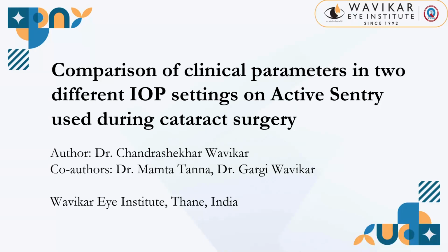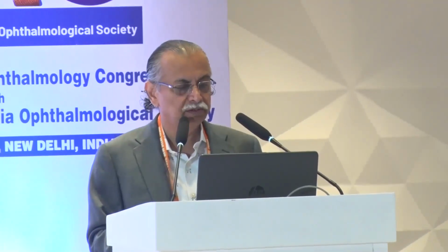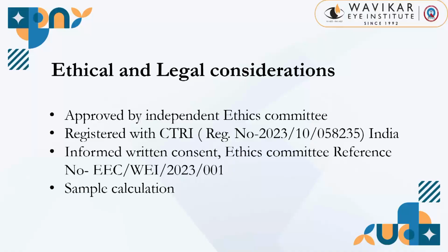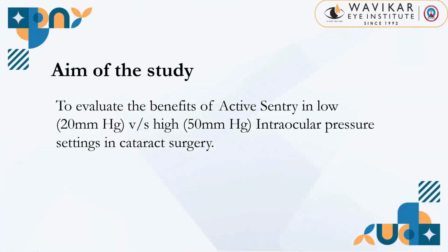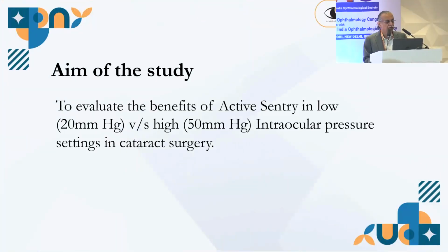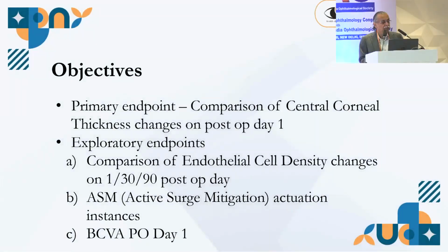Good morning, everybody. I am going to talk on comparison of clinical parameters in two different IOP settings on active Centurion machine. It was funded by Alcon. All the ethical and legal considerations were met. The aim of the study was to evaluate the benefits of active Sentry in low, that is 20, versus high, that is 50 millimeters of intraocular pressure during phacoemulsification.